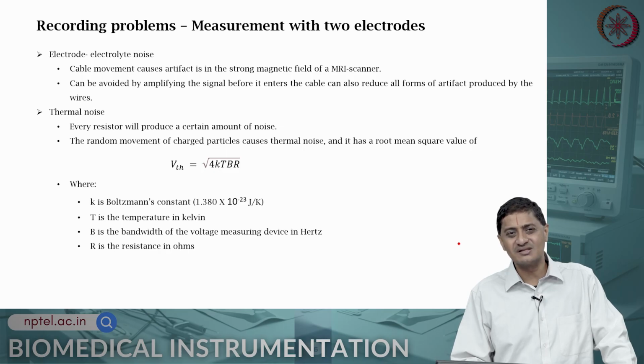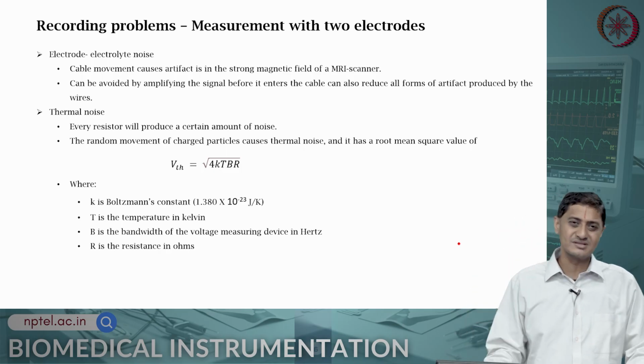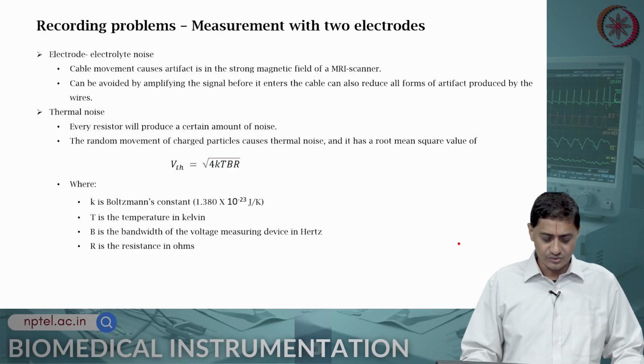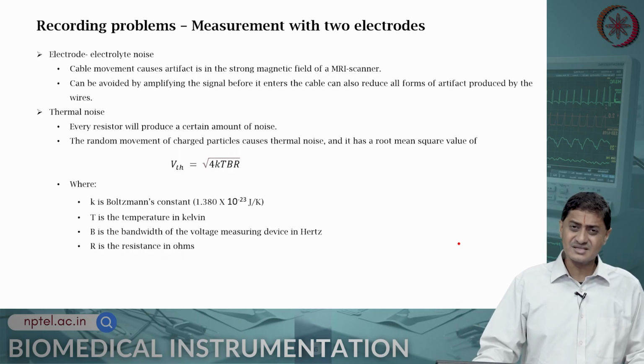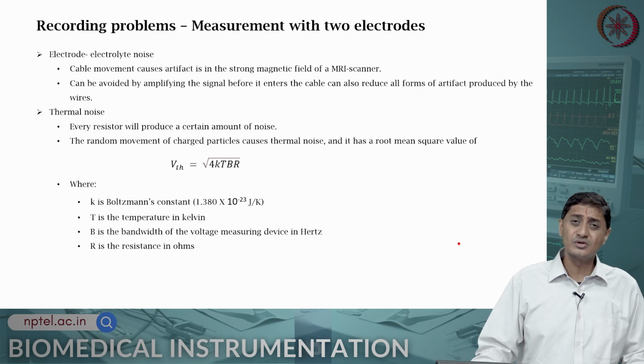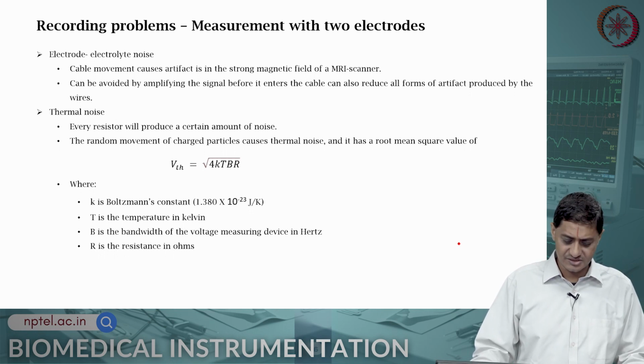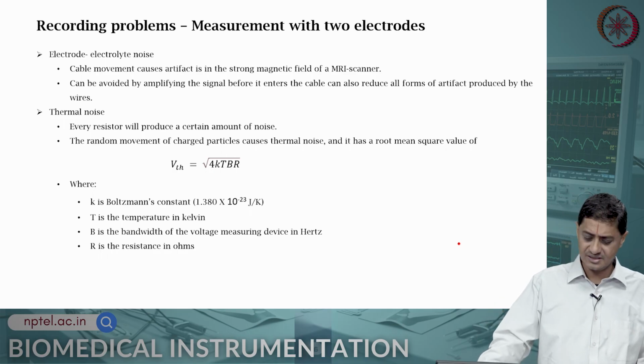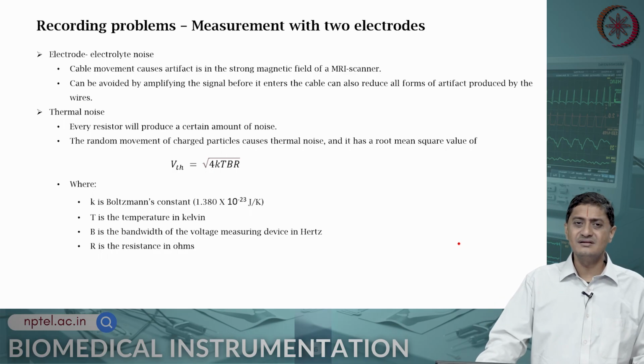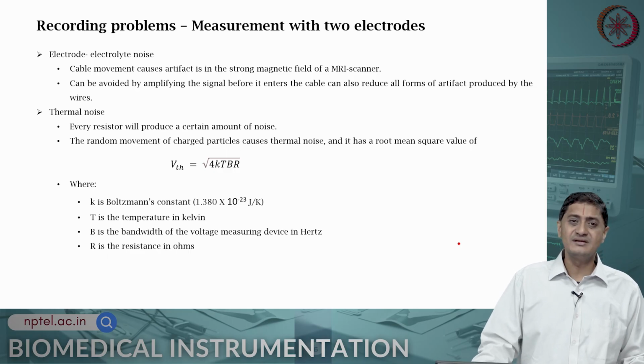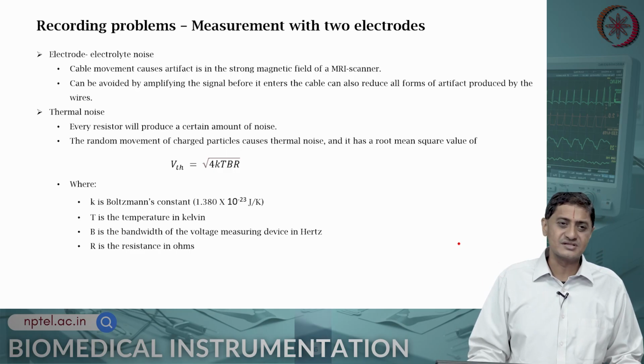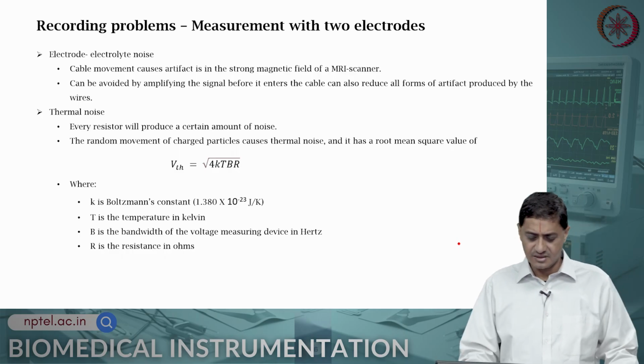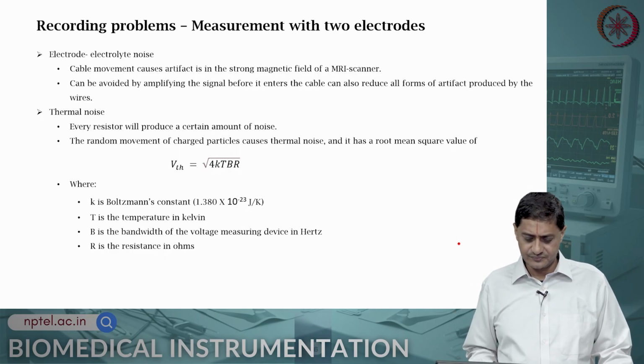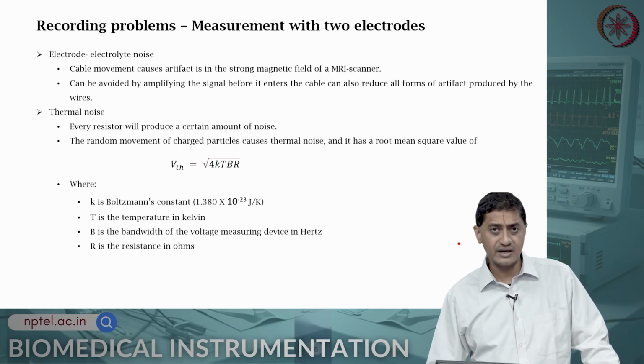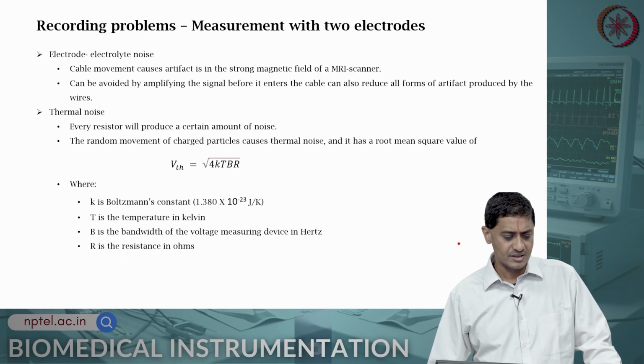All cables will have resistance, and all resistances will produce a certain amount of thermal noise, and that is related by the formula: V thermal equals the square root of 4kTBR, where k is the Boltzmann's constant, which is 1.38 into 10 power minus 23 joules per Kelvin, T is the temperature in Kelvin, B is the bandwidth of interest, and R is the resistance in ohms, right. And we can find out the RMS thermal noise using this formula.